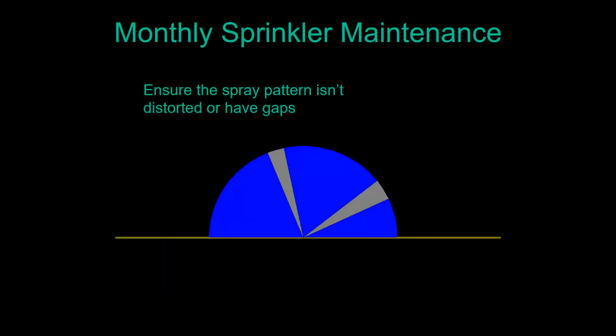The other thing for monthly sprinkler maintenance is make sure the spray pattern isn't distorted or has gaps. Your standard spray nozzle is just a slit where the water comes out, and if there's a little bit of debris in there, it's not very large, but you'll see as it moves out into the pattern where that sprinkler head covers, that gap gets bigger and bigger where you're not getting any water applied. We actually call those fingering nozzles, because very often you'll end up with just fingers of water coming out of there.